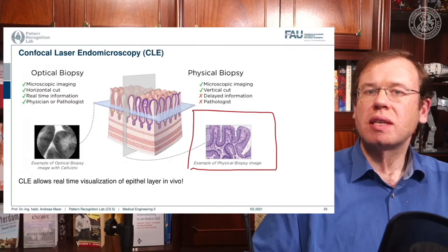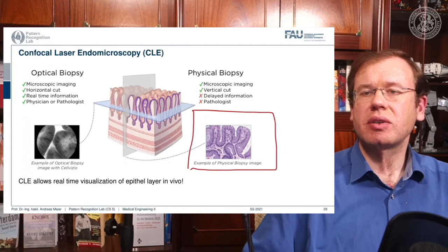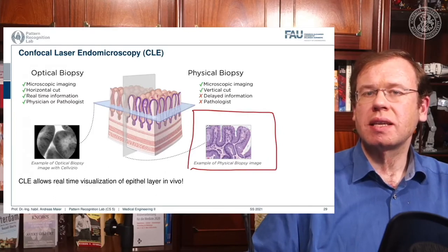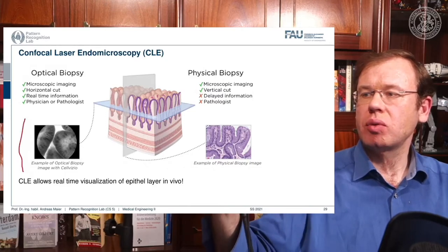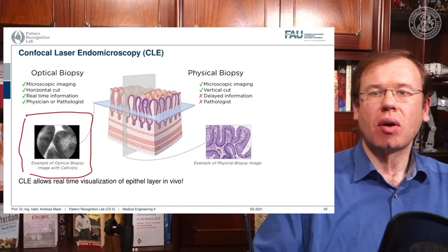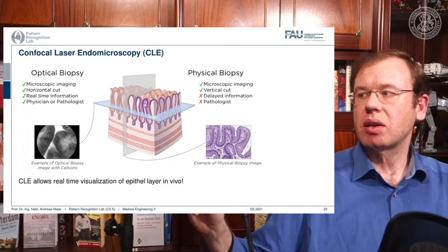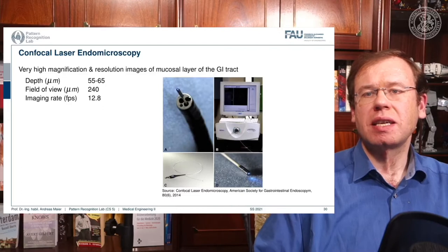From a standard biopsy image you can identify different cells, identify cancer, and go into the cellular range to identify any processes going wrong. However, this takes time because you have to take out the tissue, stain it, cut it, and run the microscope. The CLE is the idea of doing that inside the body, taking views essentially at a microscopic level to differentiate individual cells, with a field of view of about a quarter millimeter and imaging depth of approximately 50 micrometers.